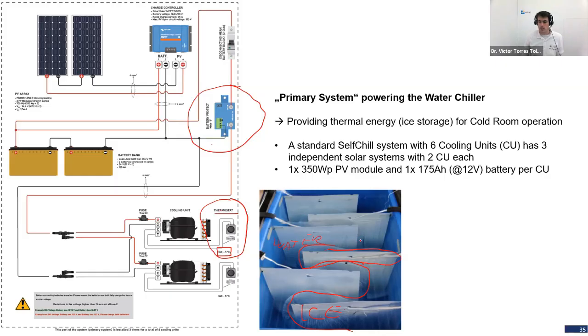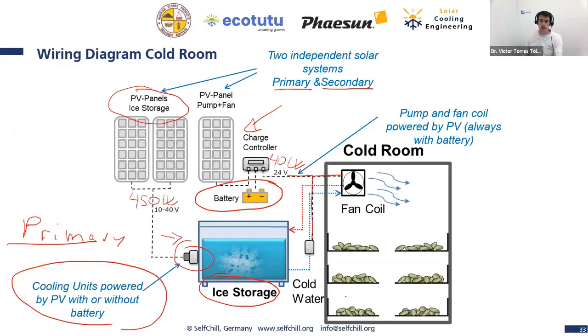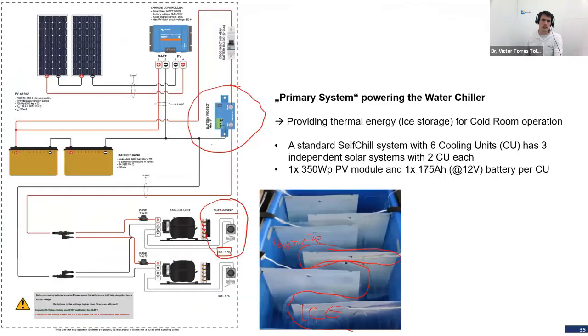But this water chiller is closed anyway, so the whole system is closed. As you could see here, this is a closed circuit. The water goes from the water chiller through the water pump to the fan coil and comes back. The water chiller is closed, so normally this water doesn't get dirty. If you put clean water inside, it stays clean for always. Sometimes you have to introduce a little bit more water, but I would say this is not critical. Thank you for the question.